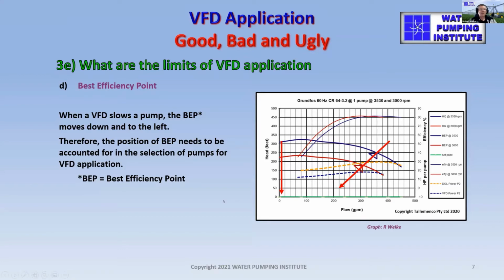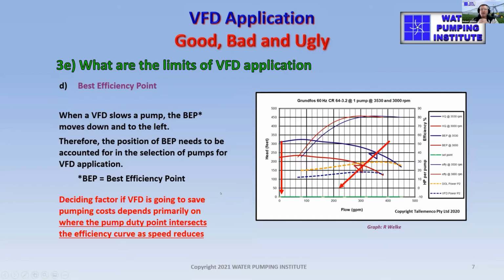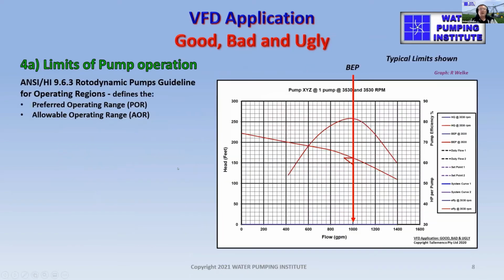overall final efficiency. So the deciding factor if a VFD is going to save pumping costs depends primarily on where the pump duty point intersects the efficiency curve as the speed reduces. So we've got to, at this point, refer back to what is the efficiency at the duty where the pump is being slowed to. So we're familiar with this graph on the left. I've just demonstrated it, but let's look at some limits of pump operation.